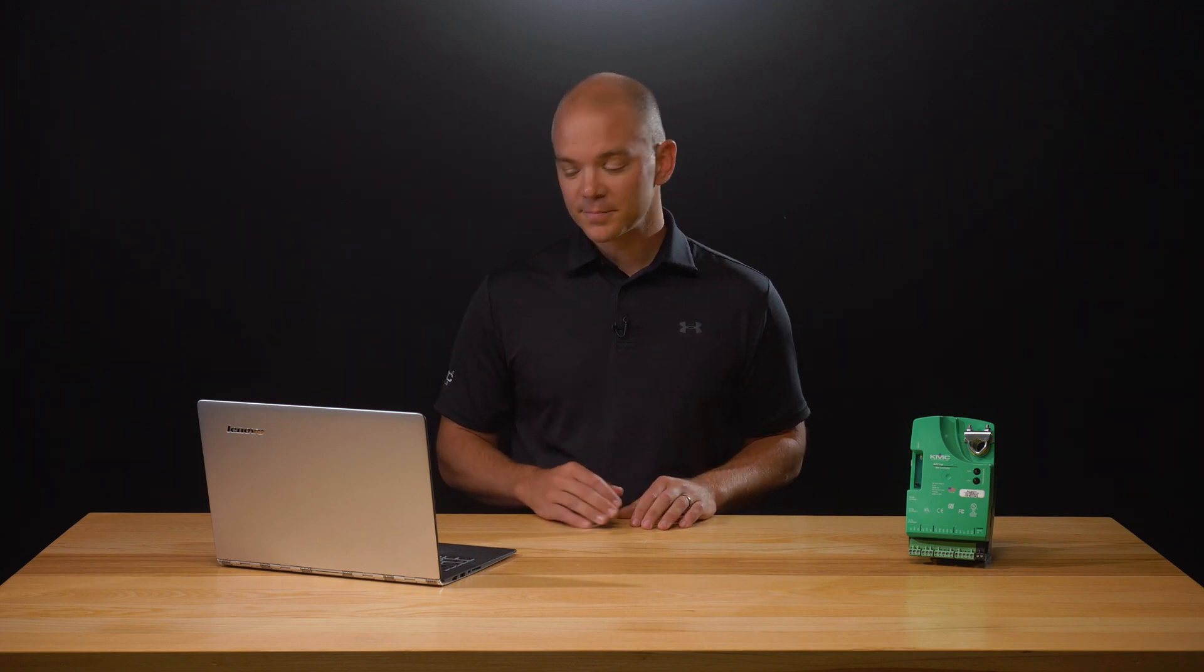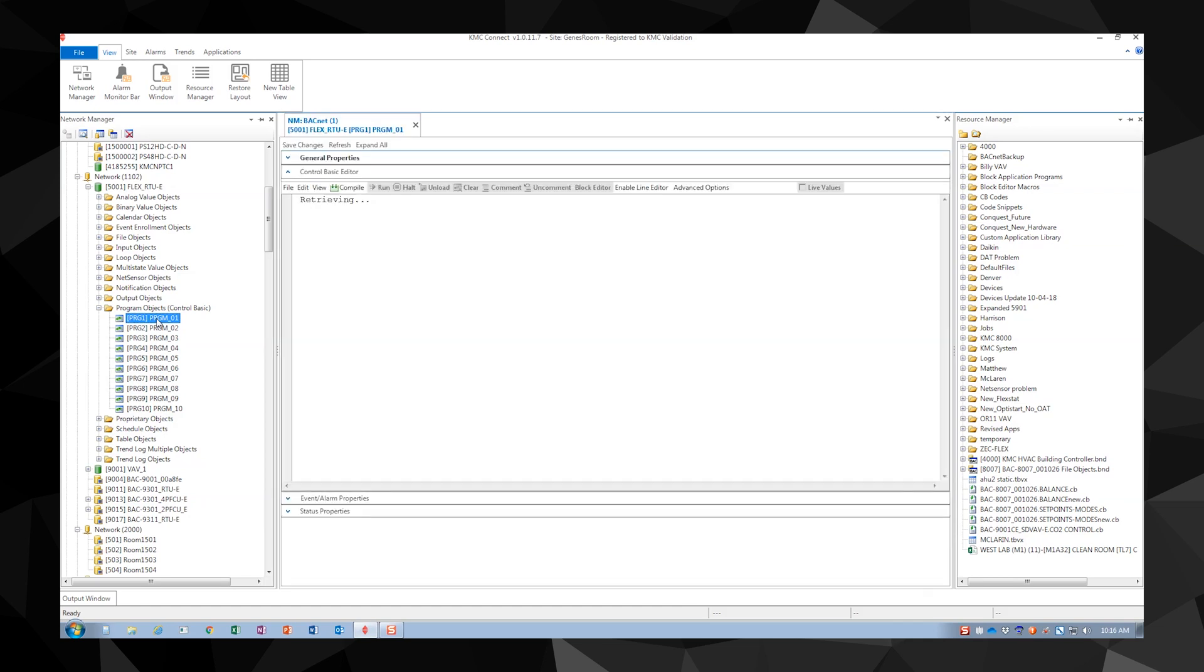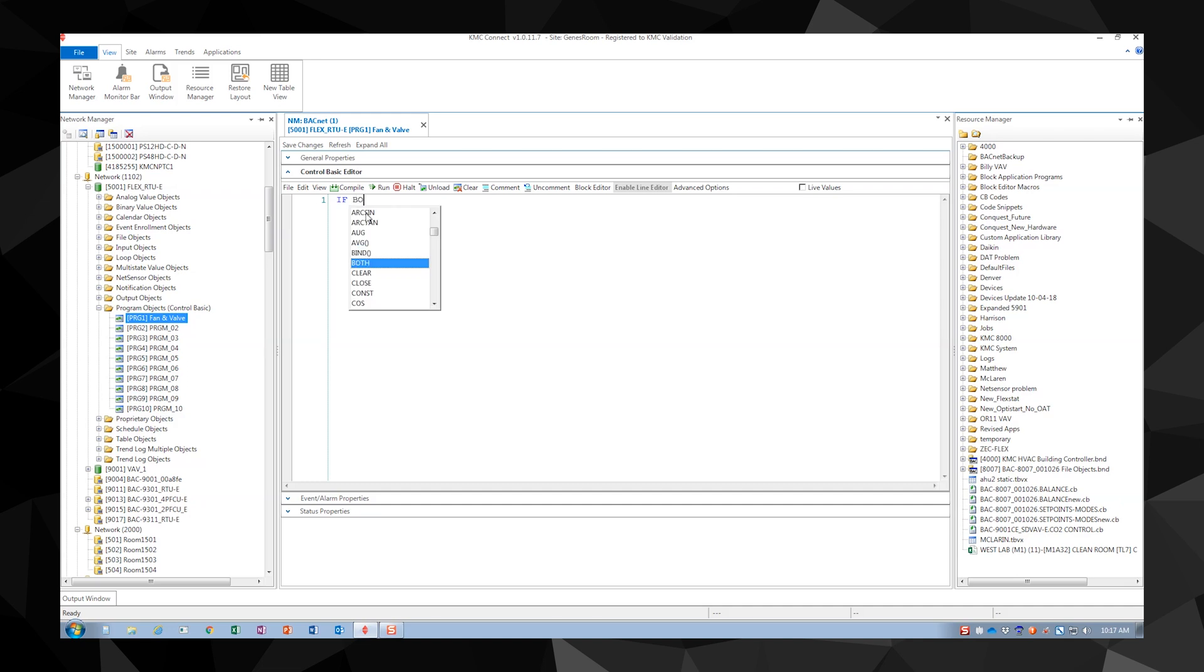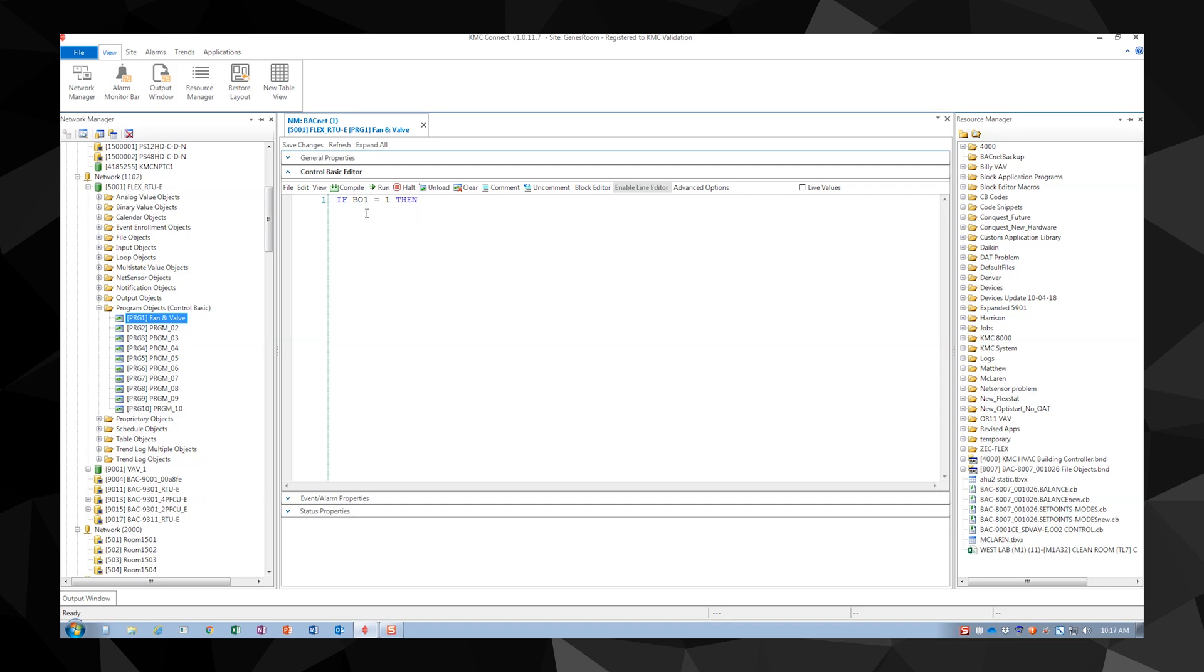Let's look at our first example of a simple Control Basic program. Open a new program. Here we're going to control a fan and modulate a valve based on whether or not the fan is running. If the fan is running we want the valve to be at 25%. The fan is controlled by B01 and the valve is driven by A07.